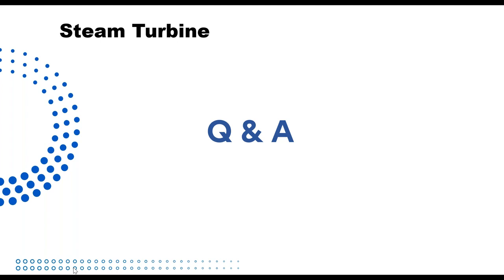Okay. And from the same person, what's the turn down on the turbine? Each is a little bit different. You know, maybe a 4-to-1 turn down ratio at best, maybe 5-to-1 depending, but certainly it's something that we would look at. If there is a range of steam flow, we want to make sure we know what those upper and lower limits are, so we can look to design the turbine so that it's operating almost 24/7 as much as possible.